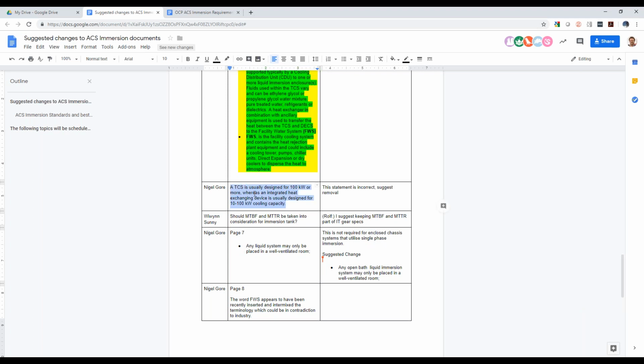The TCS is usually designed for 100 kilowatts or more, whereas an integrated heat exchanging device is usually designed for 10 to 100 kilowatt cooling capacity. You're saying this statement is incorrect, suggest removal - correct. I did confuse TCS here with a CDU that facilitates multiple racks. Sure, but there are CDUs on the market that can support up to 305 kilowatts at the moment. So if we put a limiting figure into it - no, it's 100 kilowatts or more, below 100 kilowatts you're not going to... so if you're doing 50 kilowatts you're not likely to use a CDU that facilitates multiple racks.